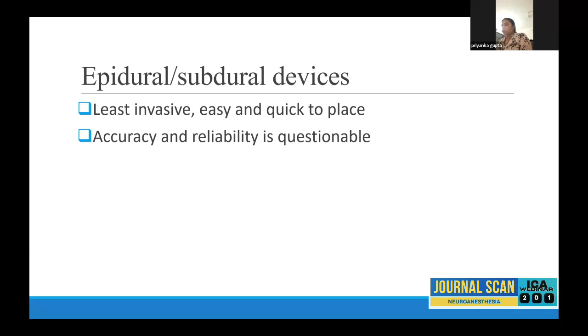Then comes the Spiegelberg pneumatic sensor. This type of sensor can be placed epidurally, subdurally, intraventricularly, and intraparenchymally. And one of the main advantages of this catheter is that it can be zeroed in vivo. Other than this, no other currently available intraparenchymal monitor can be re-zeroed. Once they are zeroed, their zero drift will be there. Here, every hour, it can automatically zero itself. So this is also a fluid-filled catheter transducer system. Rather than the external strain gauge, which we have seen in the intraventricular and subarachnoid techniques, here that strain gauge, that Wheatstone bridge, is itself placed inside the catheter.